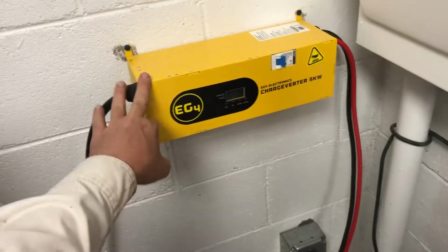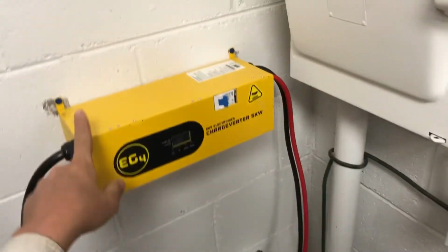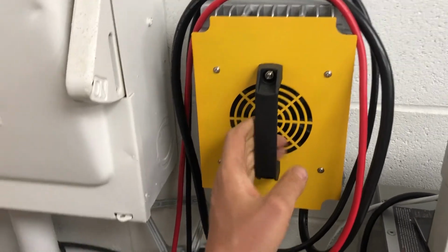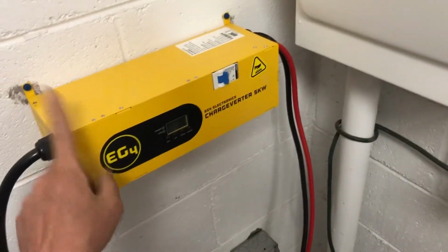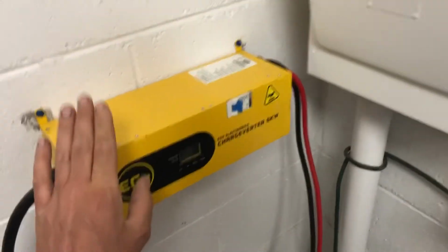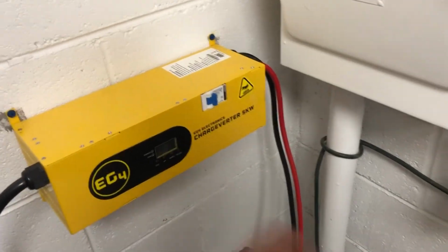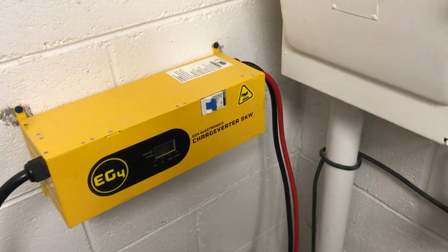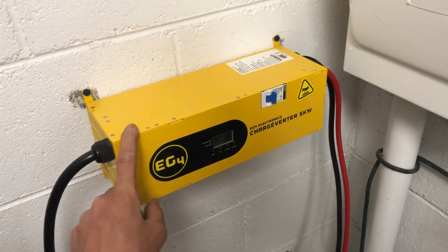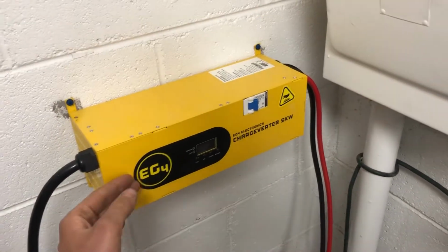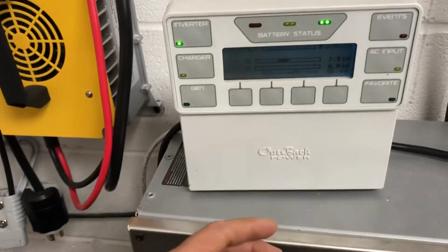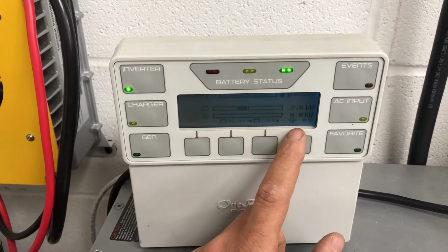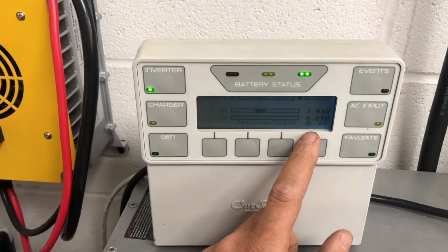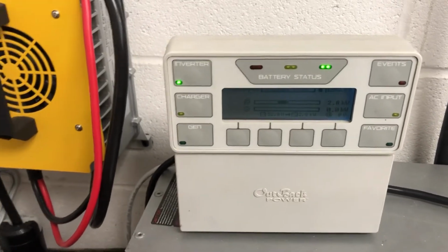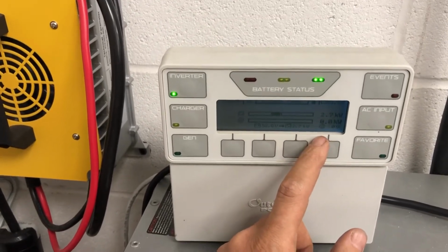So when this charger dies, the client can immediately switch over to this charger while we get parts for this one. I like this one a lot better because when the batteries reach a full state of charge, this charger tapers back its output to the draw of the inverter. The output of that charger is a little bit more than 2,000 watts. Like we're at 2.8 right now, so we're probably drawing about 800 watts from the inverter.